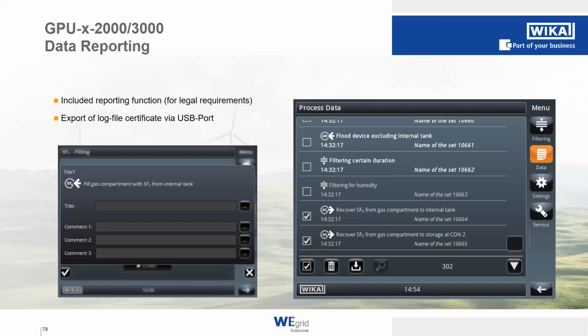The differentiation between these two is that the system log is for a much longer period, just logging which process has been chosen, has it been aborted before it ended automatically, and a certain sequence of the processes which have been chosen. In the event log, which is for a shorter time frame, everything is logged: which valve has been opened, which valve has been closed, what was the pressure level, how the pressure has developed at a certain timestamp. This data gives us, for repairs or for service, a very thorough insight of what has happened in the machine, and of course shortens all repair time and all the clearing of the process.